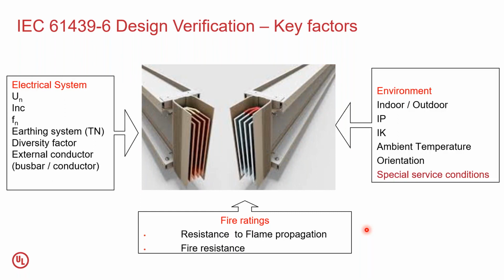That is because, as we all know, when we perform the temperature test, the busways by default are tested in a horizontal orientation, unless the manufacturer also wants to declare the vertical orientation. And finally, because bus bar trunking systems pass from one room to another, one building to another, in case of any fire there is a high risk of the fire being transmitted from one building to another, one room to another.